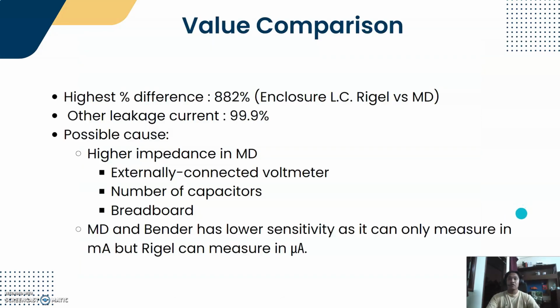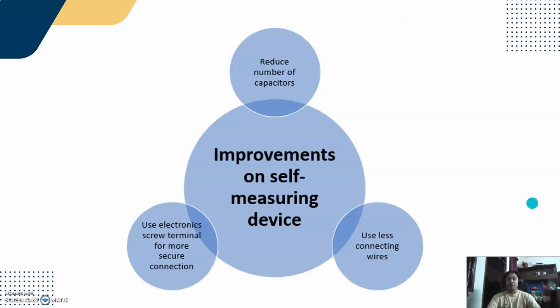The highest percentage difference is 882%, which is enclosure leakage current between the measuring device and Rigel, while other leakage currents have 99.9% difference. High percentage differences may be caused by higher impedance in our measuring device due to the externally connected voltmeter, number of capacitors, and breadboard. Also, our measuring device and Bender have lower electrical sensitivity as they can only measure up to milliampere. So, we propose several suggestions to improve our measuring device. First, reduce the number of capacitors to reduce impedance. We can also use fewer wires and use electronic screw terminals for a more secure connection.